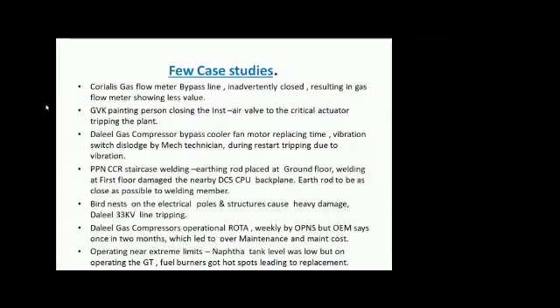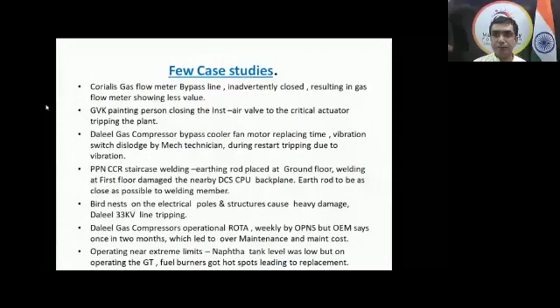So what happened in one of the cases is that inadvertently, some person slightly opened that manual bypass valve. Some of the gas was passing through. Of course, the machine did not get any effect, because it was getting the actual line gas required. But on the metering side, some part of the gas was going through the gas flow meter, and some part was going through the manual bypass.